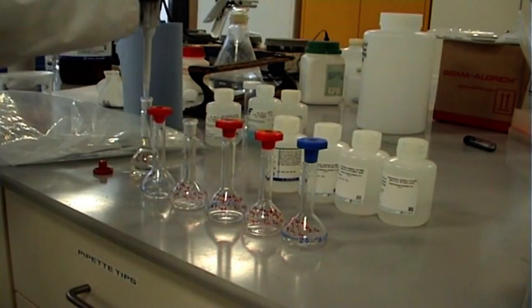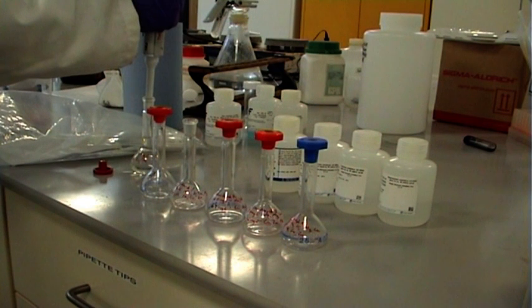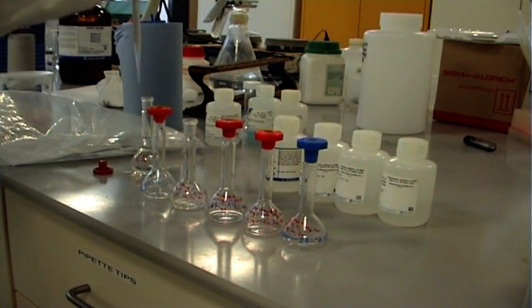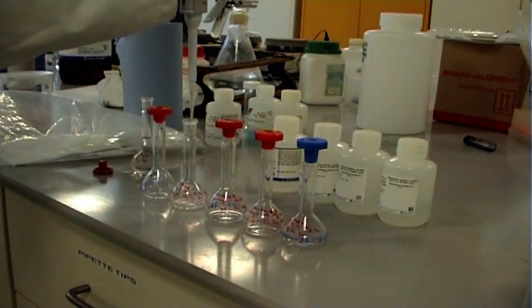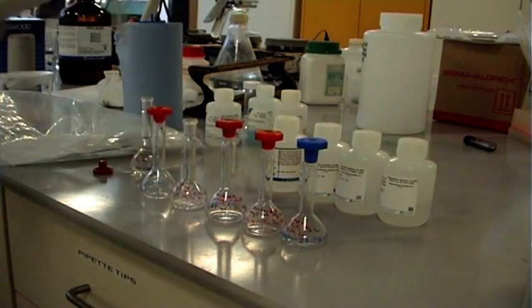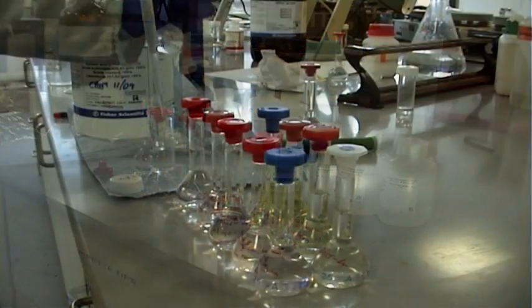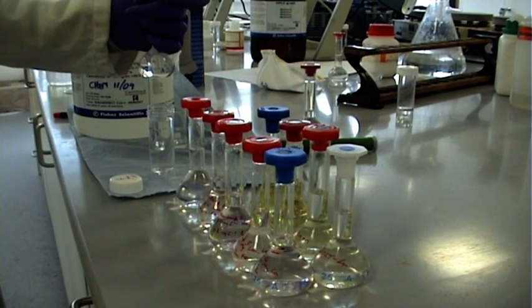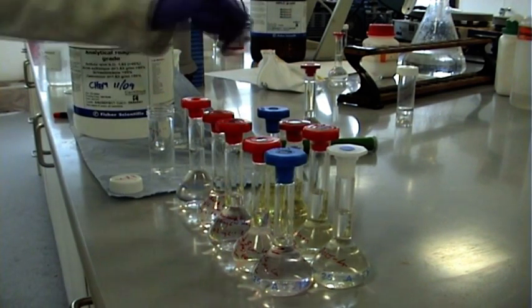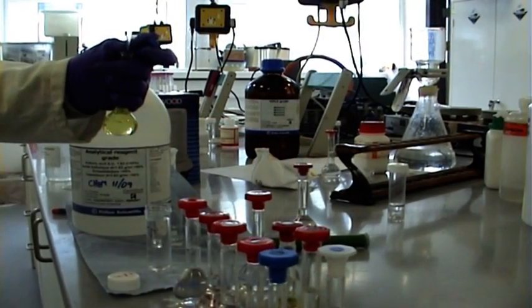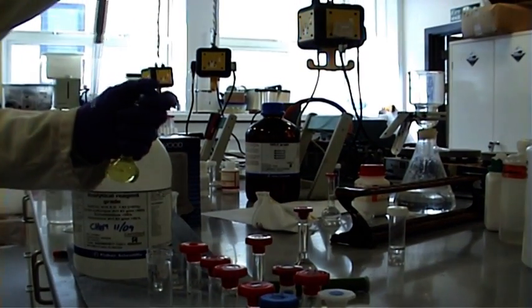We can now prepare our calibration standards using, in this case, single calibrant solutions of known concentration of the analytes of interest. Before making up to their marked volume, the acids used in the digestion are also added to match their concentration found in the sample digests. The flasks are then made up to the mark and mixed by inversion.